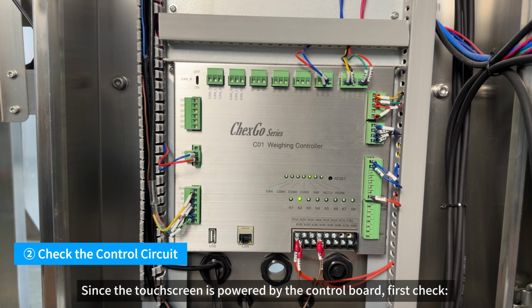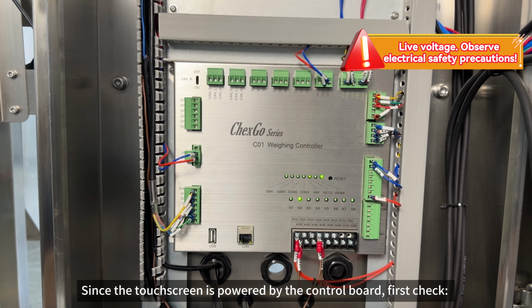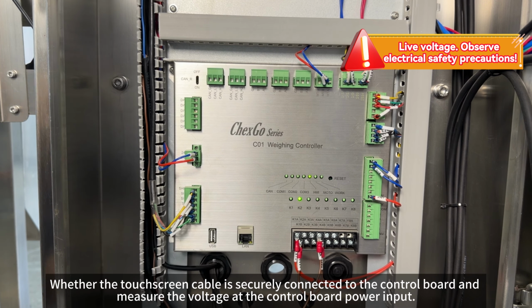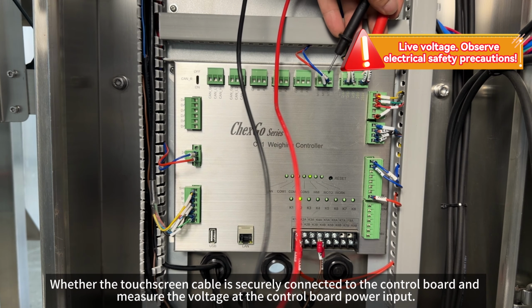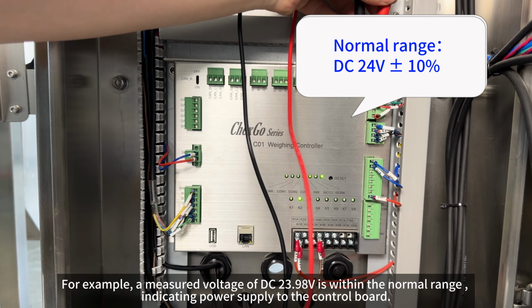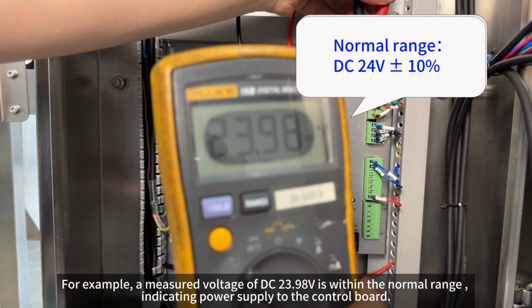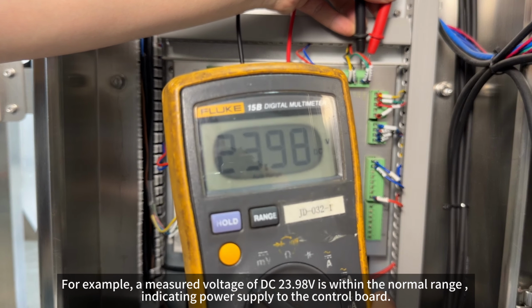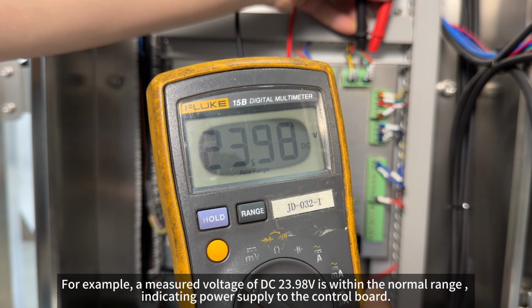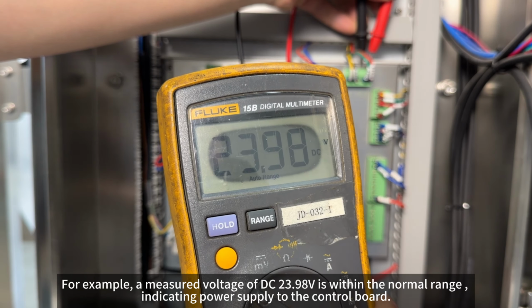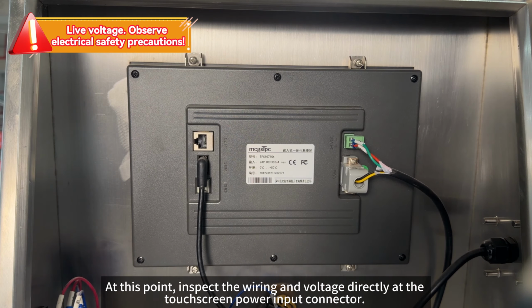Since the touchscreen is powered by the control board, first check whether the touchscreen cable is securely connected to the control board and measure the voltage at the control board power input. For example, a measured voltage of DC 23.98 volts is within the normal range, indicating power supply to the control board. At this point, inspect the wiring and voltage directly at the touchscreen power input connector.